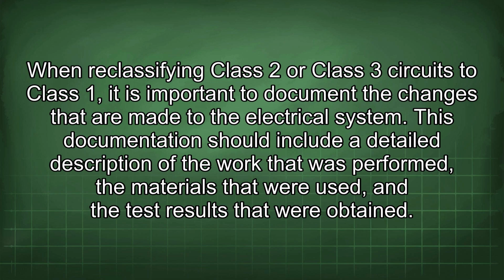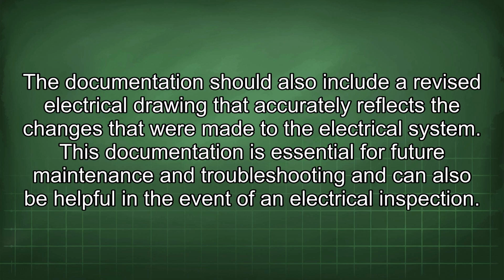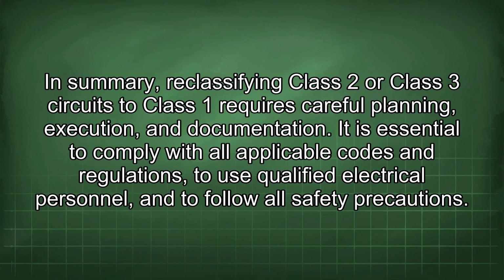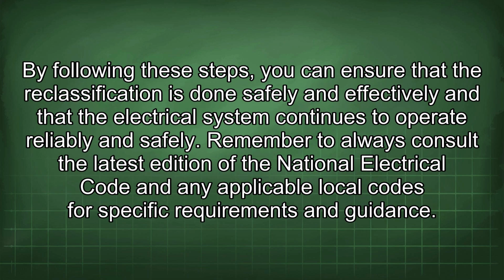When reclassifying Class 2 or Class 3 circuits to Class 1, it is important to document the changes that are made to the electrical system. This documentation should include a detailed description of the work that was performed, the materials that were used, and the test results that were obtained. The documentation should also include a revised electrical drawing that accurately reflects the changes that were made to the electrical system. This documentation is essential for future maintenance and troubleshooting and can also be helpful in the event of an electrical inspection. In summary, reclassifying Class 2 or Class 3 circuits to Class 1 requires careful planning, execution, and documentation. It is essential to comply with all applicable codes and regulations, to use qualified electrical personnel, and to follow all safety precautions. By following these steps, you can ensure that the reclassification is done safely and effectively, and that the electrical system continues to operate reliably and safely.